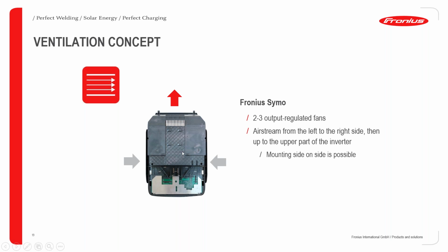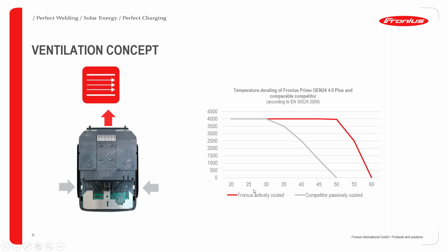By so doing, all the power electronics don't get overheated, and this helps the inverter function optimally at all times. Great. So with this, we're able to achieve what we call a high derating value. For competitors that have their inverters passively cooled, we can see that they begin to derate at a much earlier stage, in this case about 30 degrees Celsius. But our inverters actually go 100%, as in operating optimally, up to an ambient temperature of about 50 degrees Celsius.